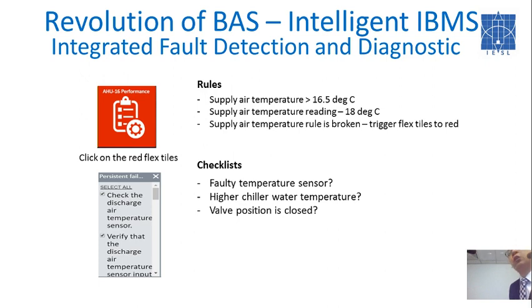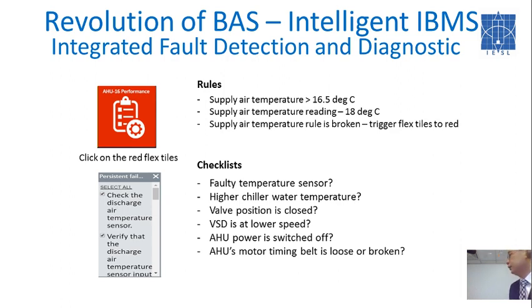Is the valve position closed for the AHU? Did someone manually override it, or change the set point itself? Is the VFD running at lower speed? That means maybe the VFD is not working fine, or somebody changed the speed itself. Is the AHU switched off? Or is the AHU timing belt loose or broken?